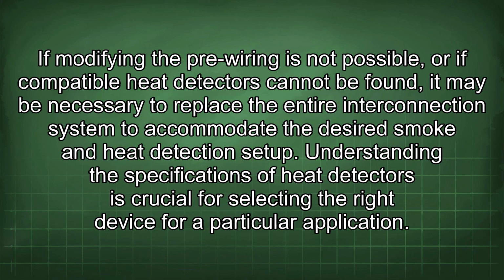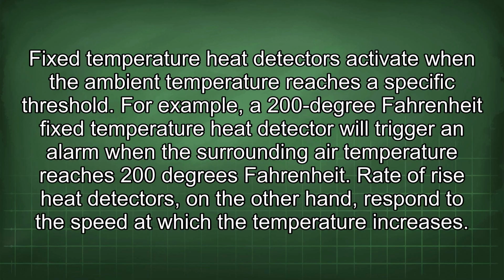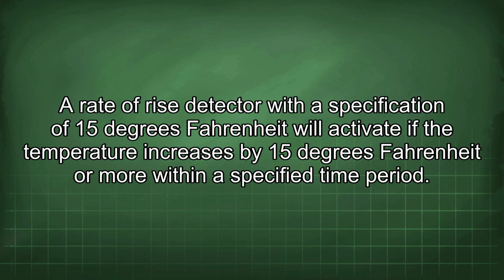Understanding the specifications of heat detectors is crucial for selecting the right device for a particular application. Fixed temperature heat detectors activate when the ambient temperature reaches a specific threshold. For example, a 200 degree Fahrenheit fixed temperature heat detector will trigger an alarm when the surrounding air temperature reaches 200 degrees Fahrenheit. Rate of rise heat detectors, on the other hand, respond to the speed at which the temperature increases. A rate of rise detector with a specification of 15 degrees Fahrenheit will activate if the temperature increases by 15 degrees Fahrenheit or more within a specified time period.